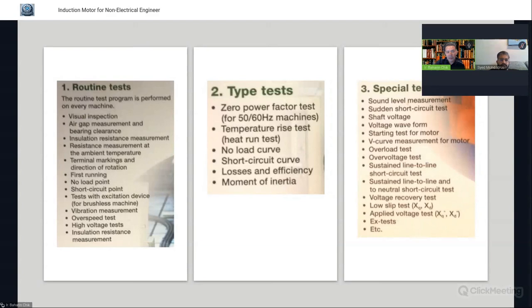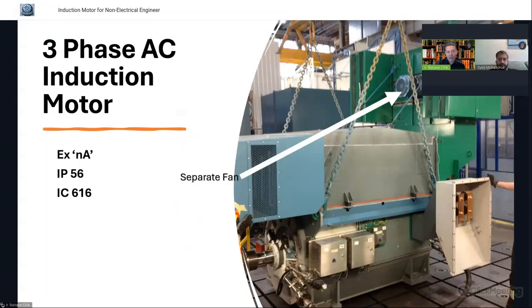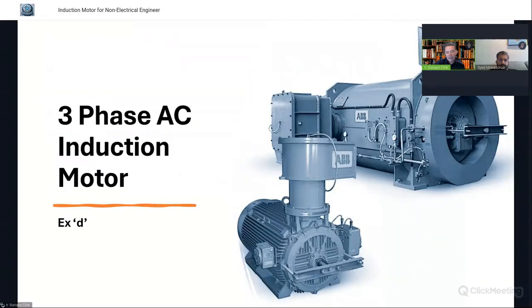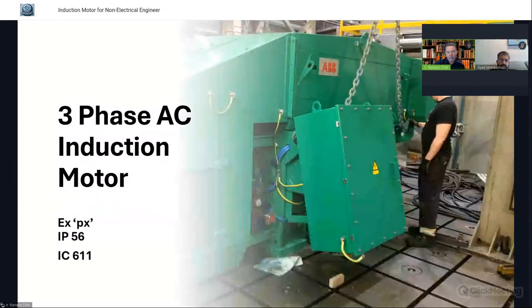So this is an example of a real project that I've done. This is an EXNA motor, with an IP rating of 56. And then this is the IC616 cooling method. And then we have separate fans mounted on the cooler. This is an EXD motor, where an explosion will occur inside the motor, and it will not propagate outside its enclosure.